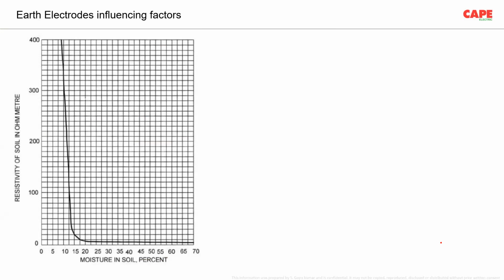Now, the other influencing factors. You can see here, the moisture in soil. Moisture in soil is a very, very influencing factor. Here on the x-axis, you can see the percentage of moisture up to 70%. Once the moisture is lesser than 10%, the resistivity of the soil increases drastically. Imagine a soil where the moisture is zero.